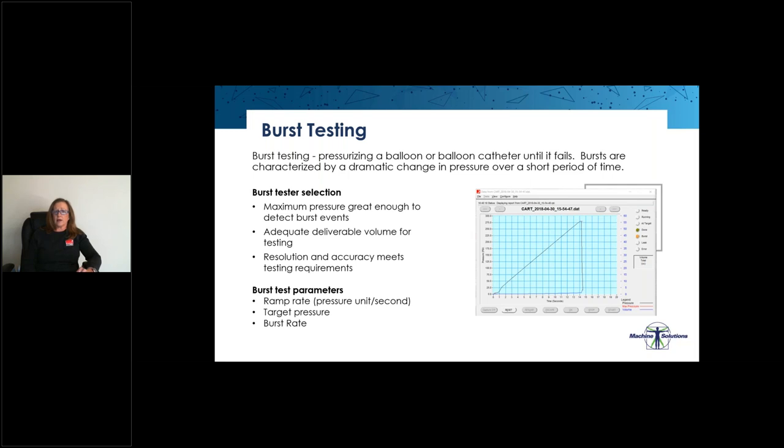Some things we want to consider in our selection are: does the tester have a maximum pressure great enough to detect burst events? Do we have adequate deliverable volume for testing? And are the resolution and accuracy good enough to meet our testing requirements?